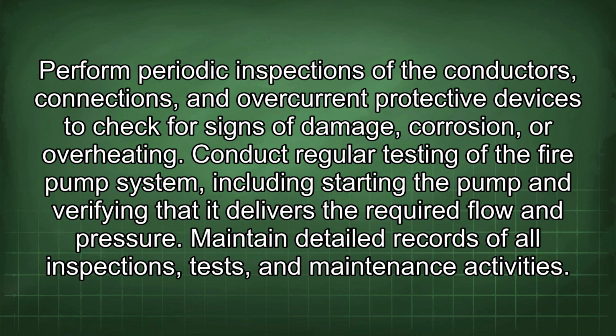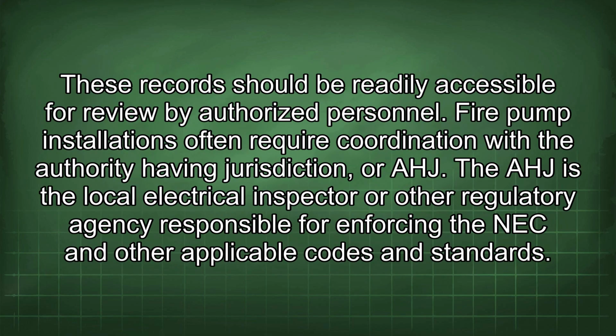Perform periodic inspections of the conductors, connections, and overcurrent protective devices to check for signs of damage, corrosion, or overheating. Conduct regular testing of the fire pump system, including starting the pump and verifying that it delivers the required flow and pressure. Maintain detailed records of all inspections, tests, and maintenance activities. These records should be readily accessible for review by authorized personnel.